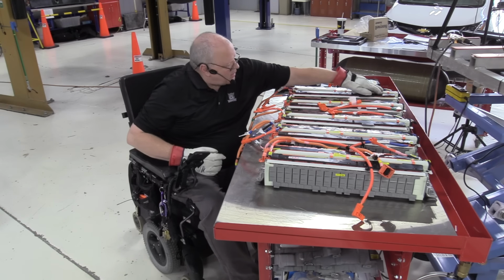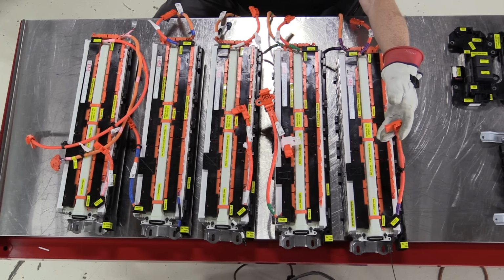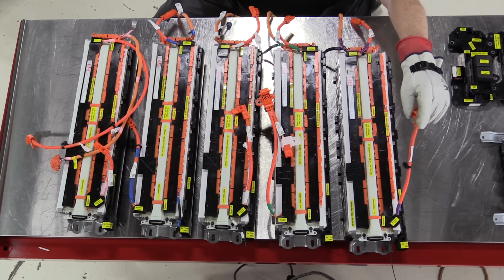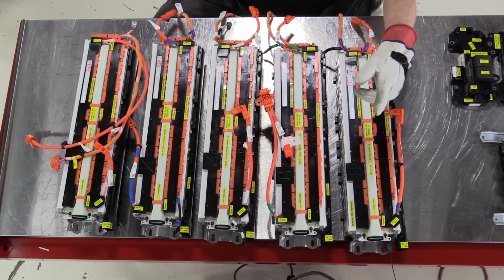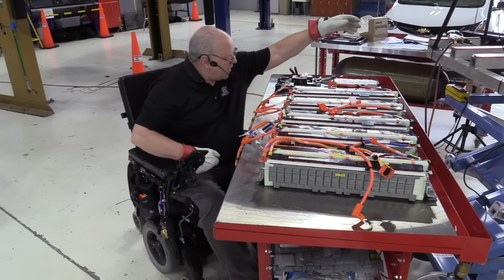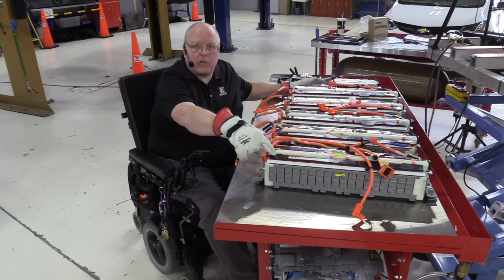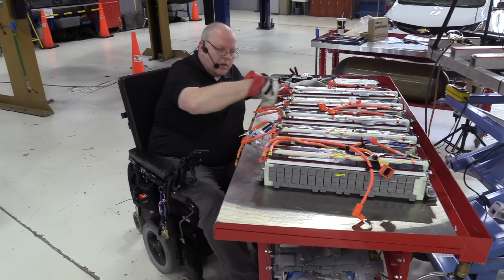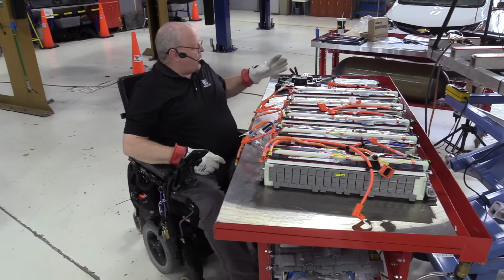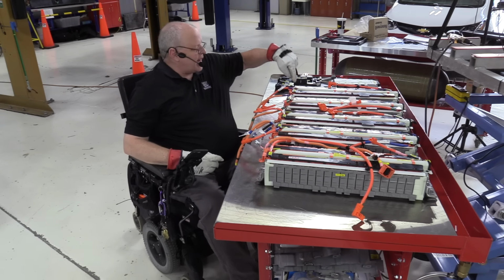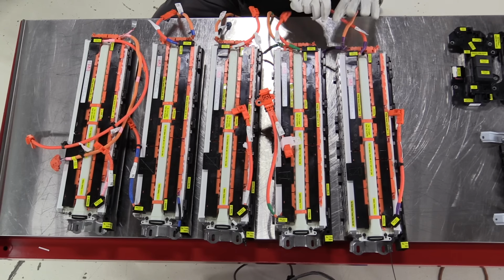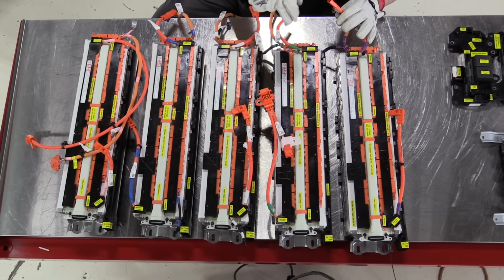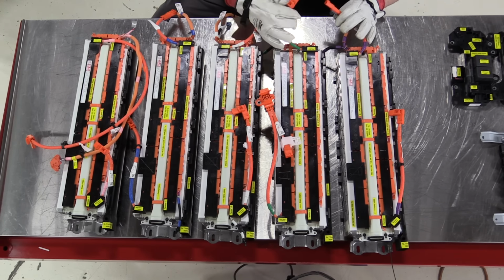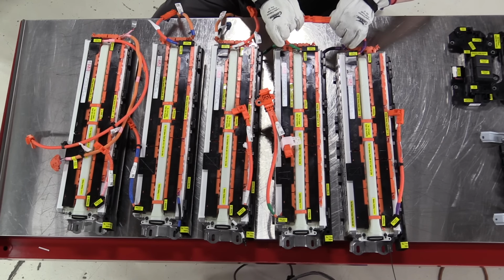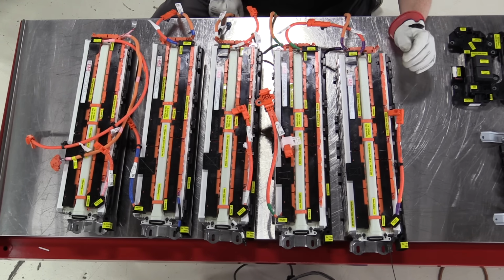On battery stack number 1, we have our negative cable, and that will connect to cell number 1. On the scan tool, when you monitor cell voltages of 1 through 95, number 1 is over here and number 95 is clear over there; they're just in series. Battery stack number 1, cell 19, has a positive terminal that connects to battery stack number 2, cell 20's negative terminal, so we'll connect those two together.